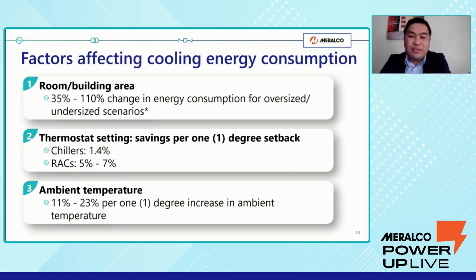Next would be the thermostat setting. I think many of us are familiar with this. It is key to know the sweet spot for the temperature of your cooling equipment. For chillers, we have 1.4% savings, and for RACs, 5 to 7% savings for every 1 degree setback. For example, if you use a 1 horsepower air conditioning unit for 1 month, 25 days, 8 hours per day, at a maximum of 16 degrees Celsius, you will probably have a monthly bill of 800 pesos. But setting it back to 17 degrees Celsius can result in monthly savings of 50 to 60 pesos. And that's just for one air conditioner. Imagine if we have many air conditioners in our homes or offices.